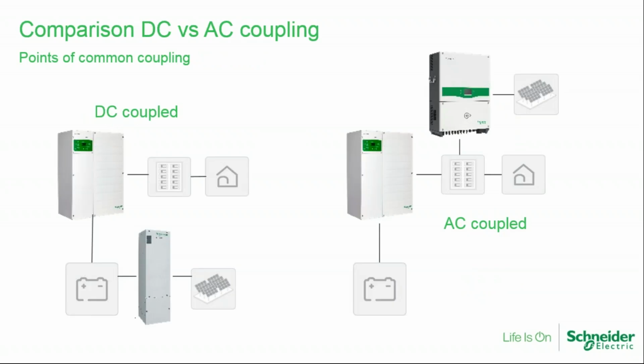So this is a comparison. On the left, there's a DC coupled system that basically takes the power that's stored in the batteries and runs the load, and then the batteries are charged by a charge controller running off the PV. And so in an AC coupled system, what we do is we charge the batteries initially off the grid to get them charged up, and then basically we will charge them from the PV whenever the grid goes away. And so the power back feeds into the output of the inverter, and then it's stepped down and applied to the battery.